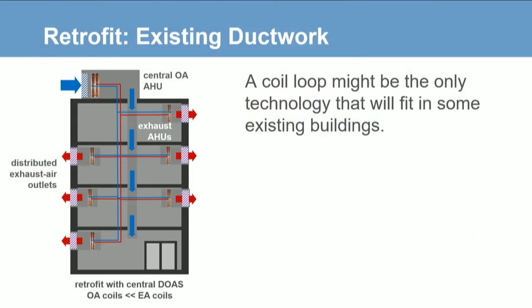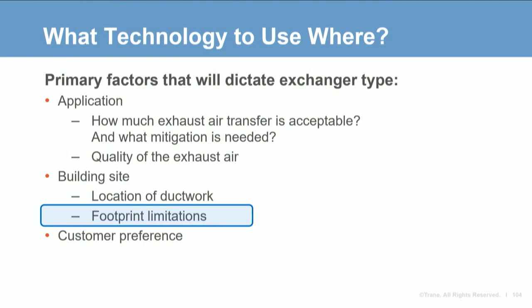The next set of factors are existing ductwork and footprint limitations. If you have an existing building with ducts and air inlet locations that cannot be moved, this often leads to using a coil loop. A 50 to 55% sensible recovery with a coil loop may not sound like much, but it will make a huge impact on peak heat demand in winter and what is required from a heat pump system. Another factor is space or footprint limitations — the answer is not as simple as one technology always fitting in a tight space, as the customer's goals for energy recovery combined with space limitations will result in different answers for different buildings.